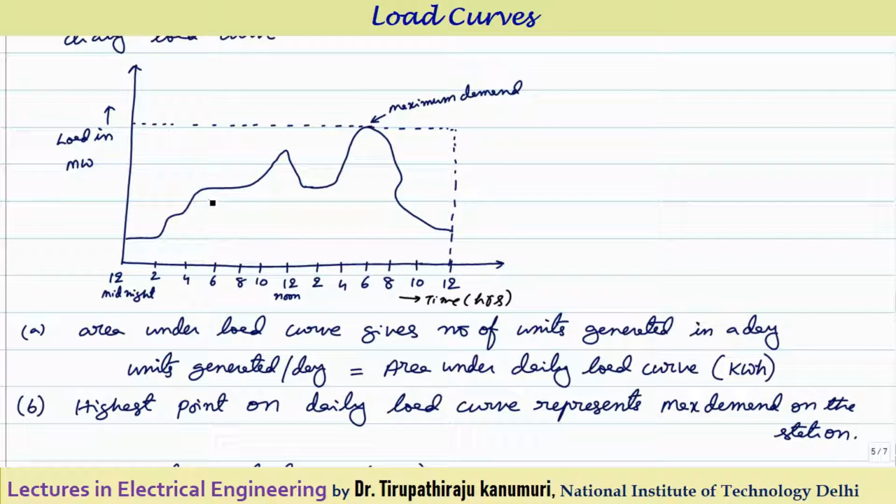So practically, instead of taking a single unit, we will select multiple small units in order to fit the load curve, such that each alternator will operate near the maximum efficiency condition. That means it will operate very near to the maximum load. Another advantage is that the extra spare unit required will be the capacity of the maximum generator unit. So automatically the cost decreases.